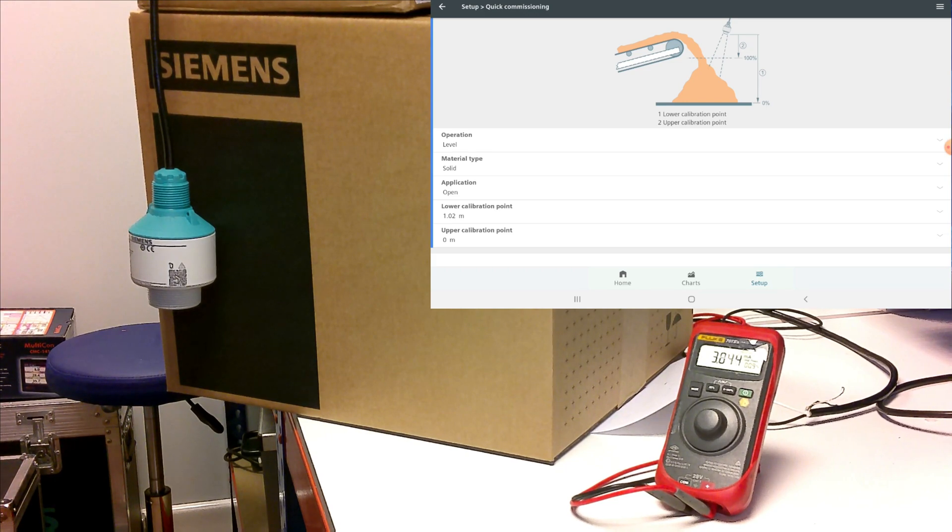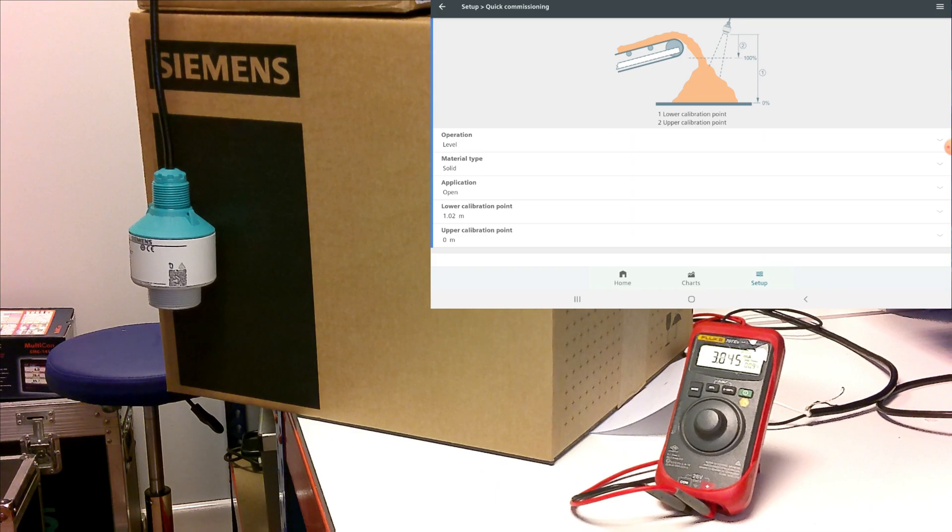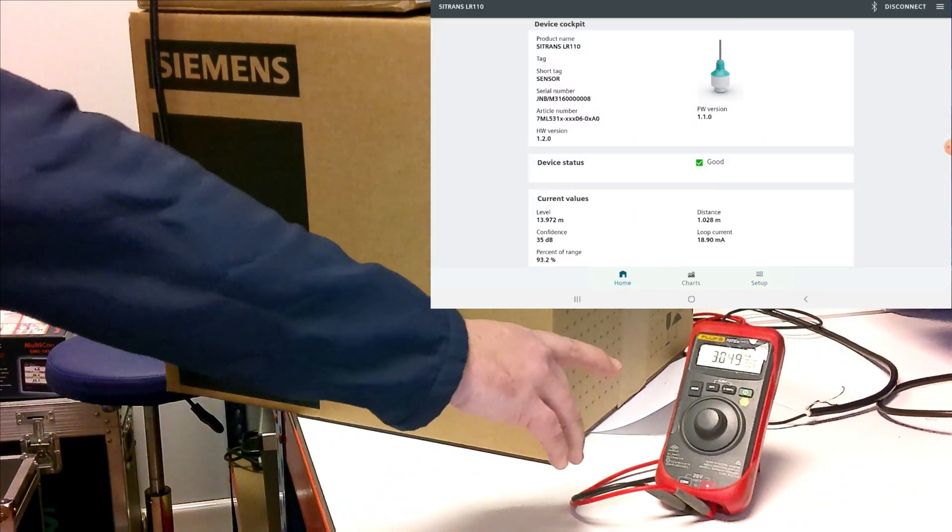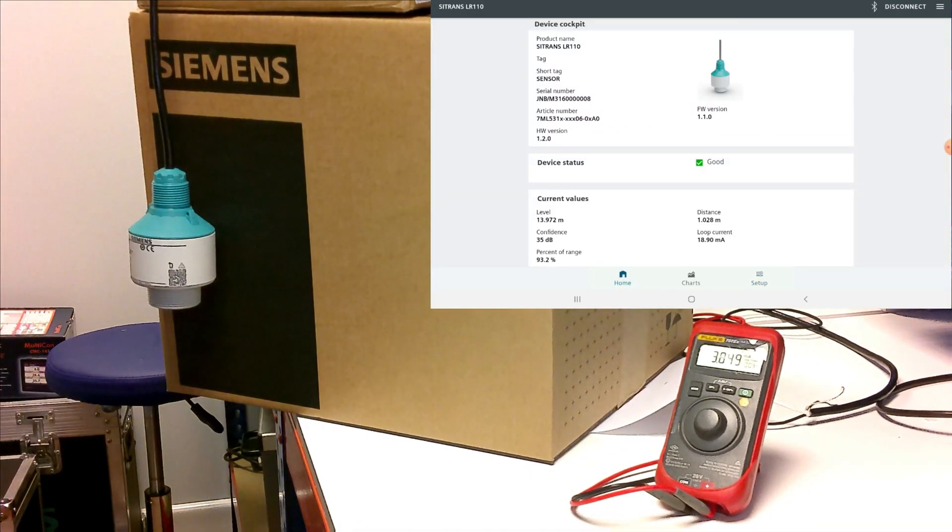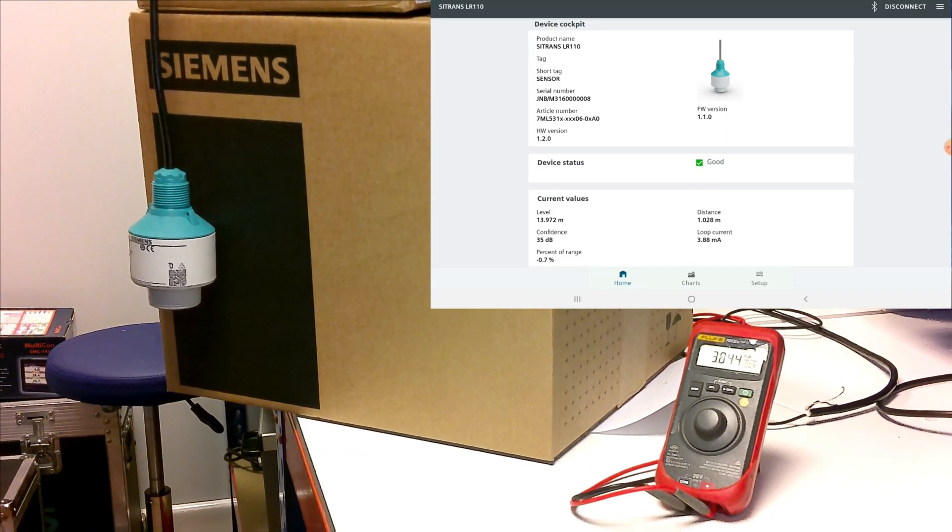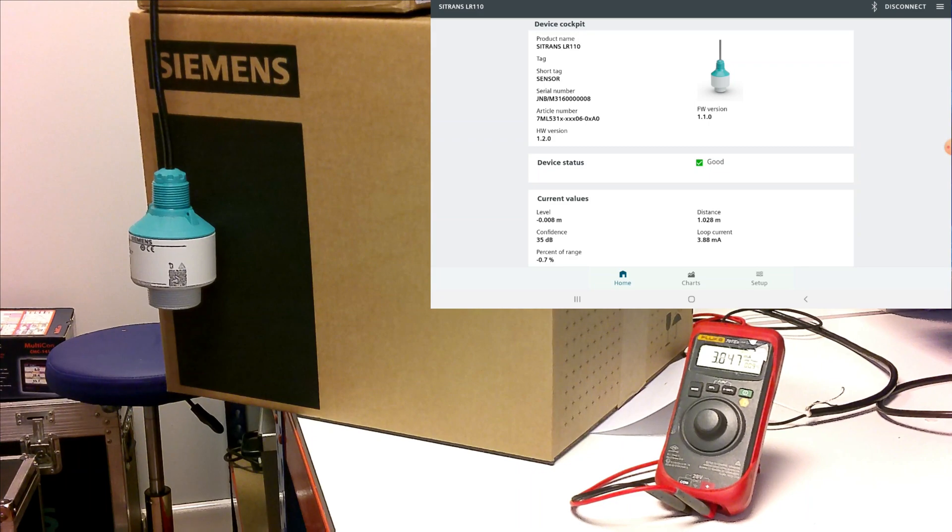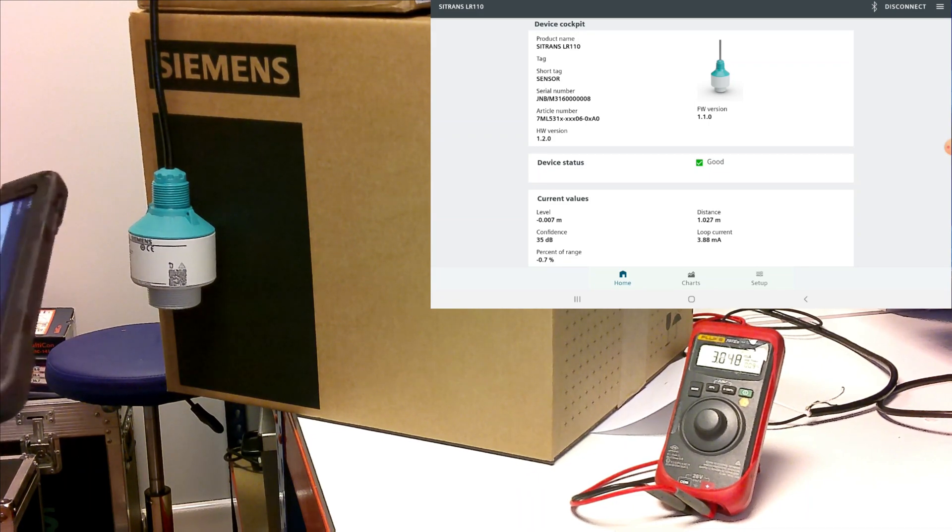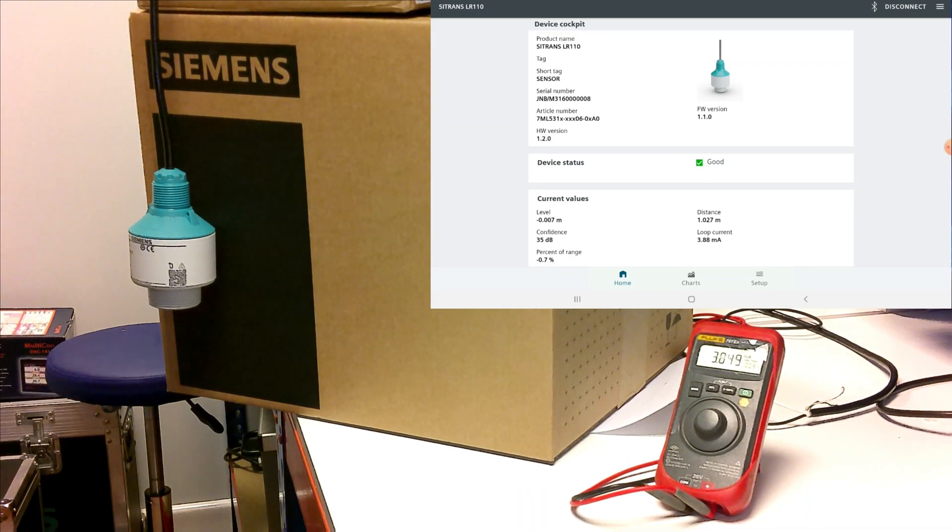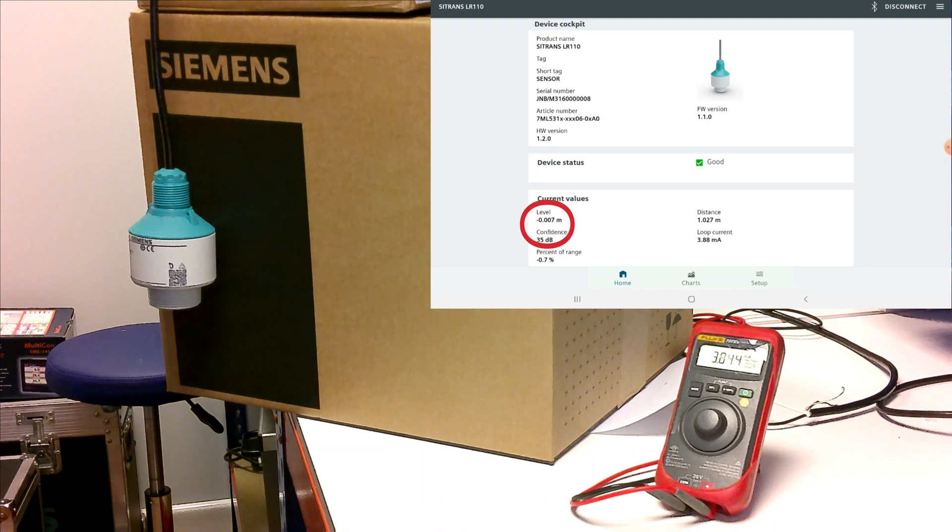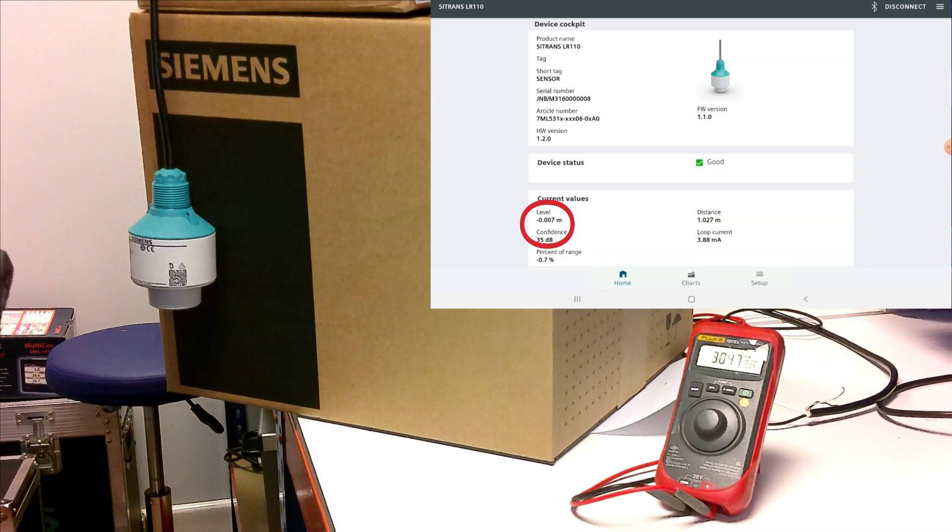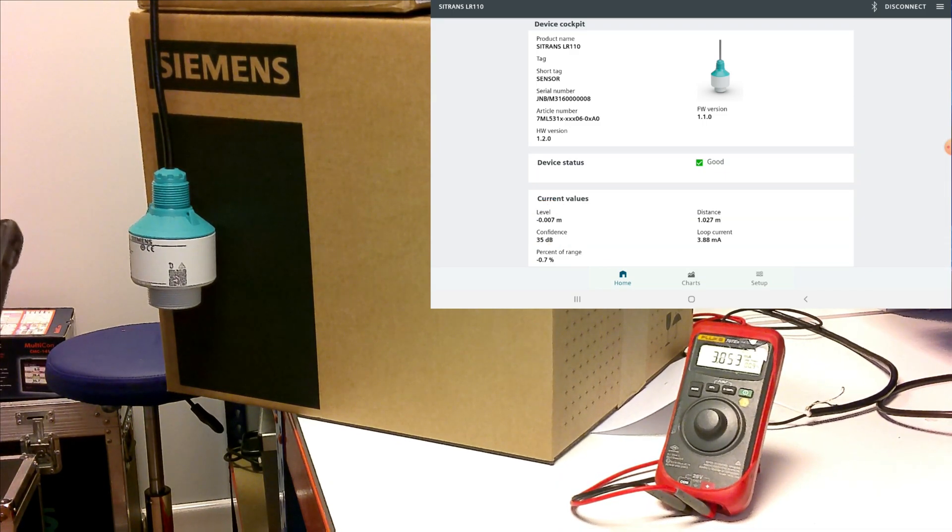And save that. We see that it sent the instruction to the device. And we can see that taking a look at our milliamp output, we've gone down to just below 4 milliamps. If we go back to our home screen on our application, we can now see that it is updated to 0 meters in level.